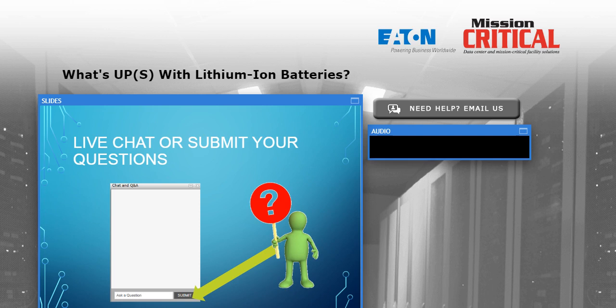So the battery will generate alarms throughout that process. It's going to say, hey, I'm a little warmer than I should be. A few minutes later, I'm still too hot, and the automatic protections have gone into play to reduce my temperature, and if the temperature continues to climb, at that point it'll give a signal that says, hey, I have disconnected myself from the string. And by the way, if this should happen with multiple batteries in the same cabinet, the entire cabinet will automatically disconnect by opening a contactor or by shunt tripping a breaker. And in the case of the shunt trip breaker, the user will have to come to that battery cabinet and physically reconnect before that battery can be used.